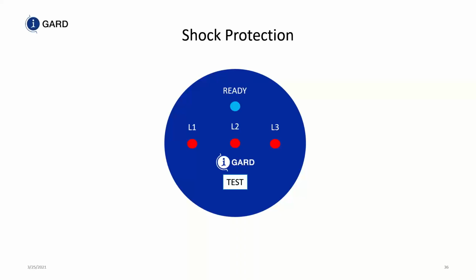What this device does is, if you have all three red LEDs, that means the voltage is present on your system. When the voltage is not present, all that happens is you lose the three red LEDs. So you press the test button, and the unit is going to go out and test phase to phase, phase to ground, AC and DC, and determine that yes, there is less than 3 volts phase to phase and 3 volts phase to ground, both AC and DC, and I've checked the meter for functionality. Therefore, I can show you 3 green lights. It is safe to enter this particular gear.